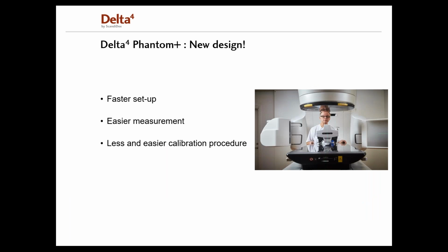So for that, ScandiDos has introduced the new Delta4 pre-treatment system. It has been redesigned from the bottom up with the next generation detector technology. The Delta4 Phantom Plus offers faster setup, where the alignment is done in seconds with clear markers on the Phantom that allow for accurate positioning of the Phantom. Easier measurements, by having the Phantom instantly ready for measurements without any warm-up. So you can just turn on the power and you are ready to measure. And also less and easier calibration procedures. I will talk more about the calibration procedures later on. And with this, the Delta4 Phantom Plus enables an efficient workflow where at least 6 complex plans can be verified within 1 hour.